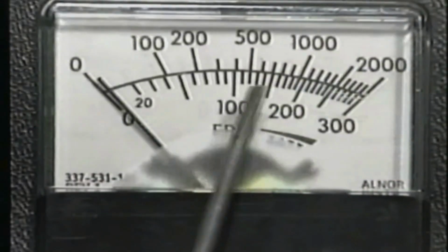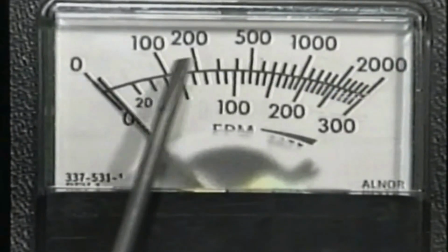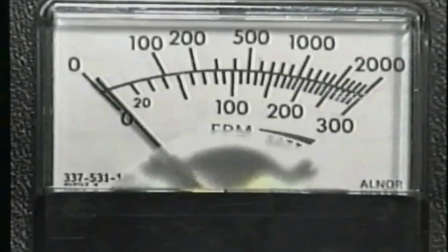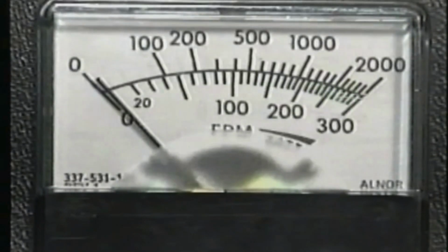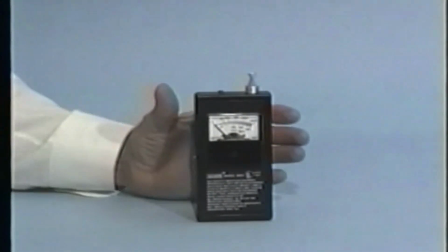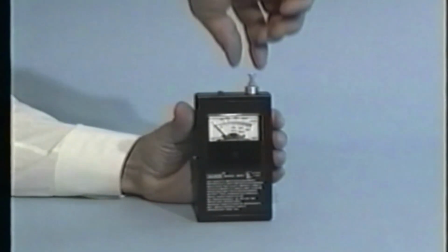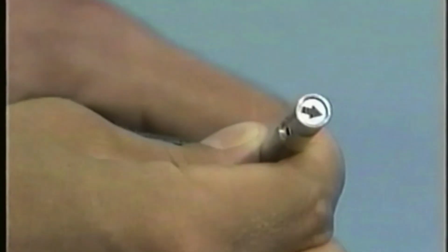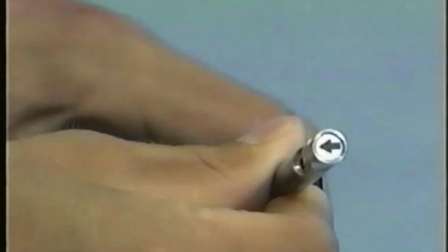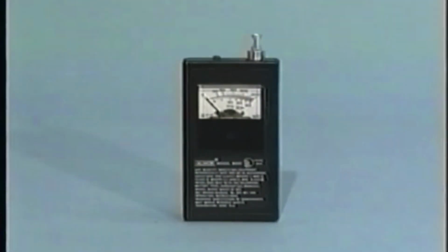In two ranges, 0 to 300 feet per minute and 0 to 2,000 feet per minute, with accuracies of plus or minus 3% of indicated reading, plus or minus 1% of scale, providing a quick response time of 2 seconds after stabilized input, temperature compensated over a range of 68 to 86 degrees Fahrenheit. And the 9850 comes with a 3-inch retractable probe that turns 180 degrees for fast, easy, thorough readings. Whatever the airflow application, if it's critical to human safety or comfort, it should not be without the Model 9850 thermal anemometer from Alnor.